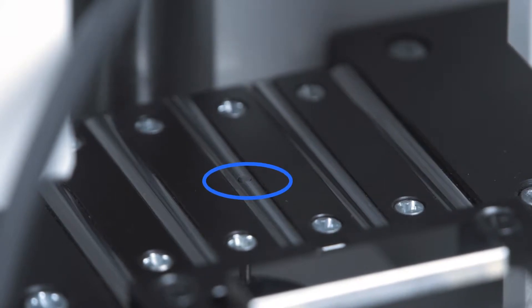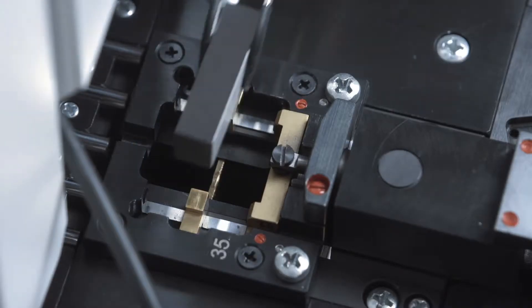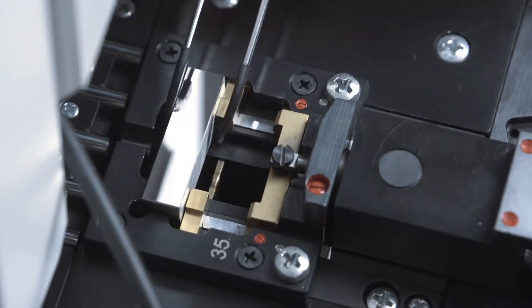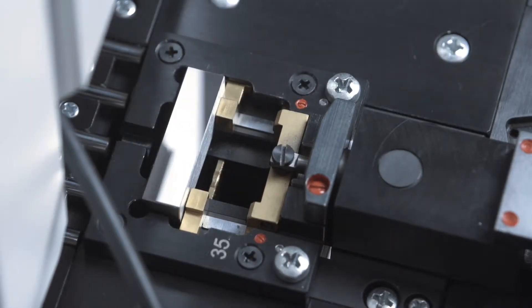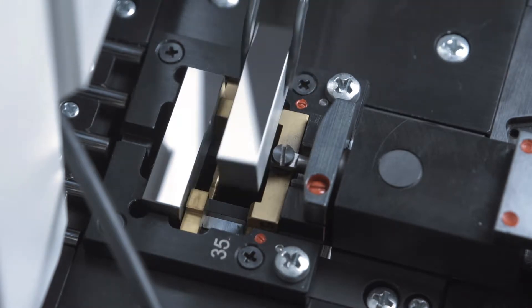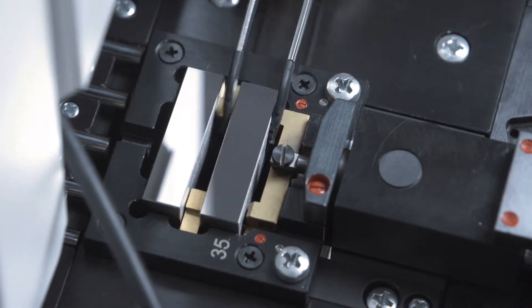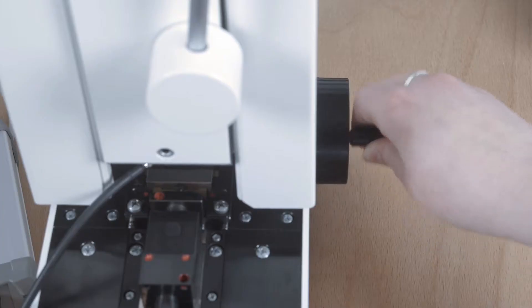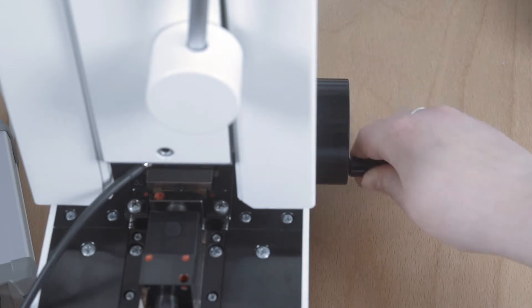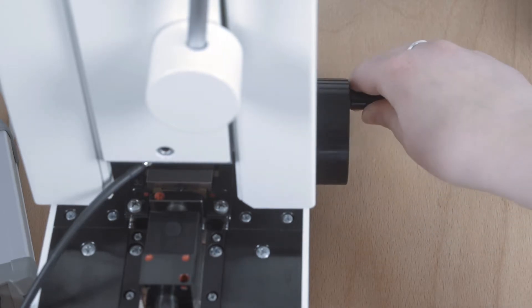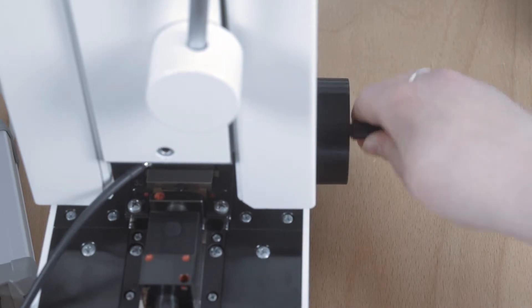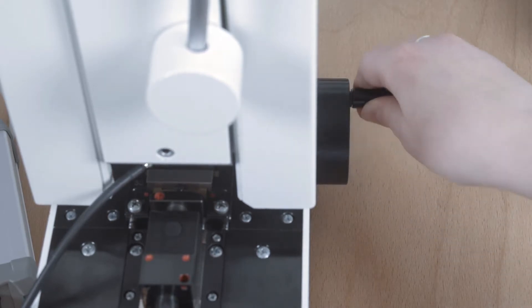The correct height is adjusted following the careful insertion of the reference and test gauge blocks into the clamping unit. This is best done whilst wearing gloves or with tweezers. Dirt and thermal influences have to be avoided during the entire handling.